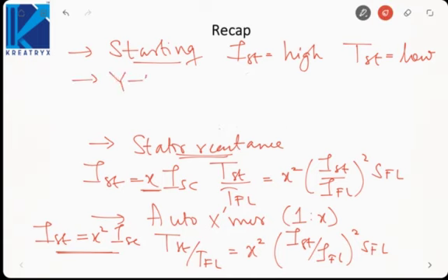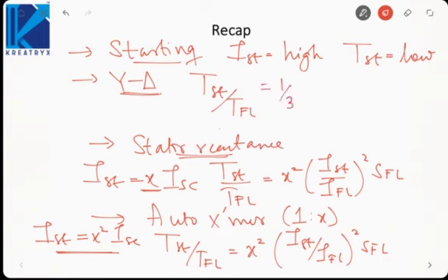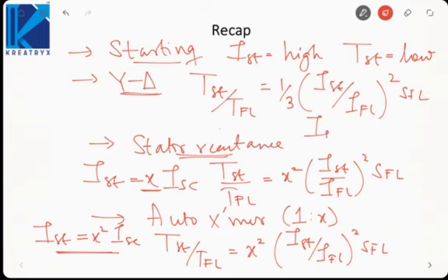The last method we saw was the star-delta starter, in which we connect the windings in star at the time of starting and in delta under running condition. The starting torque to full load torque was (1/3) × (I_starting / I_full_load)² × S_full_load, and the starting current became 1/3 times the short circuit current.